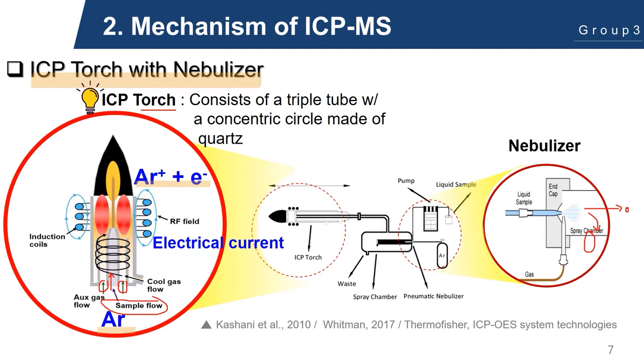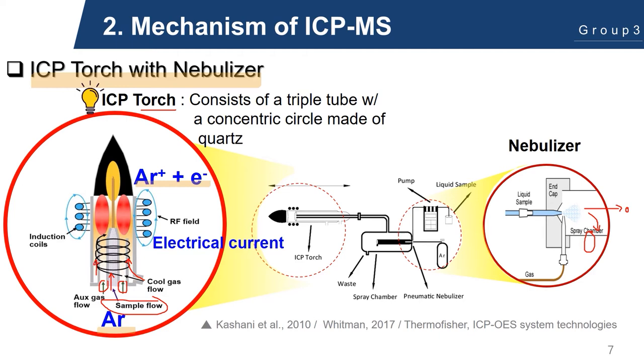At the end of this torch is an induction coil supplied with radiofrequency electric current. A high voltage discharge, also known as a Tesla spark, is applied to the flowing argon gas for a short time to introduce free electrons into the gas stream. As electrons travel back and forth due to the high alternating magnetic field from the induction coil, they ultimately collide with the argon gas, causing ionization into Ar⁺ ions. As the small sample aerosol droplets are pumped into the high temperature argon plasma, they are dried, decomposed, atomized, and finally ionized, producing a rich source of positively charged ions.